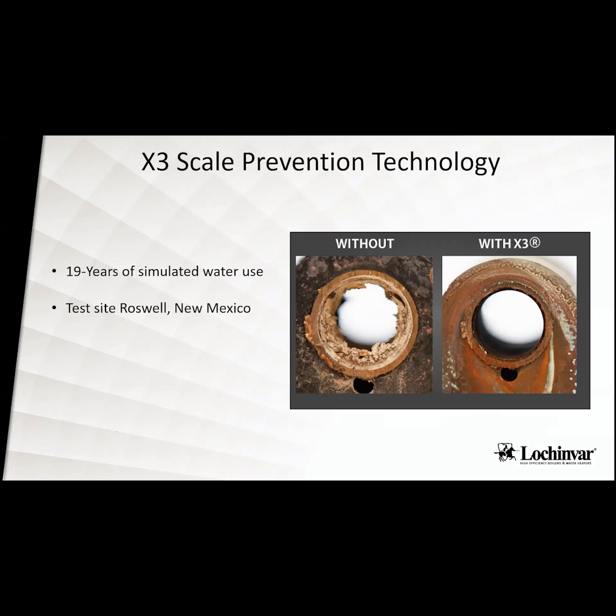Okay. So in a cabin situation, is that something we need to tell the contractor as far as winterizing? Does he need to take that scale cartridge off and drain it? Yes, he would need to take that. So he could just take that cartridge off, and they could take it with them, or they could put that coil around it. If they're not going to have any heat in that building, if they're just going to drain the system down, I would suggest taking that cartridge with them, because it'll get the water out of it, but there's still going to be a little bit of water in there. So you're not going to be able to get it all out of there.